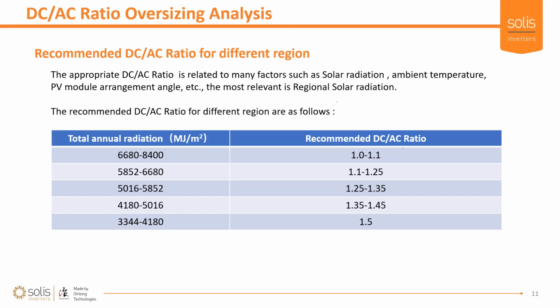I expect a question here, or I'm at least thinking of a question here. Annual radiation versus peak radiation. So for example, in the UK, in the winter periods, we get a very low radiation count, and in the summer it compensates for that in a large way and gets a lot more radiation. And so we would experience higher peaks, but our average is pulled down significantly due to the winter periods. So you would really think about the peak radiation over the annual radiation, because on those summer days when the radiation is high, the inverter's got to do that, and it's for a long period of time. It's for a solid day. So in theory, I would prefer to use a peak radiation value.